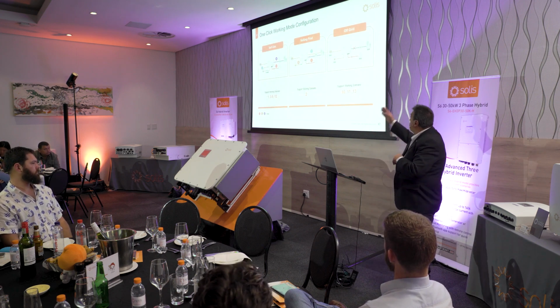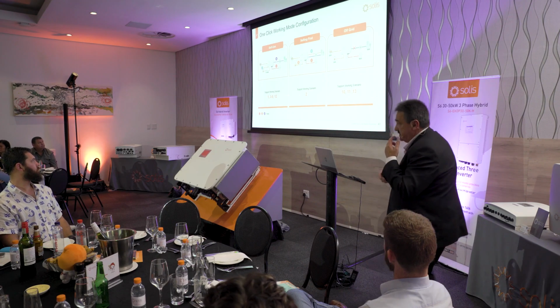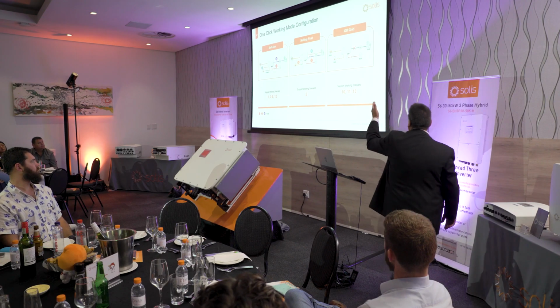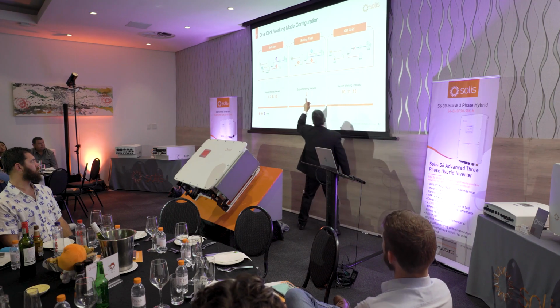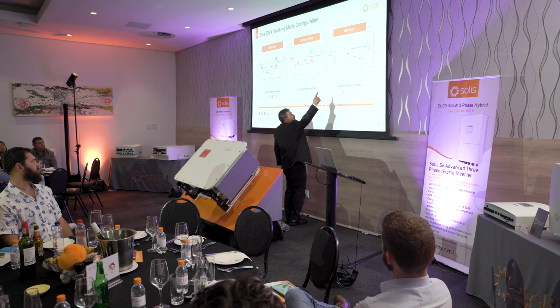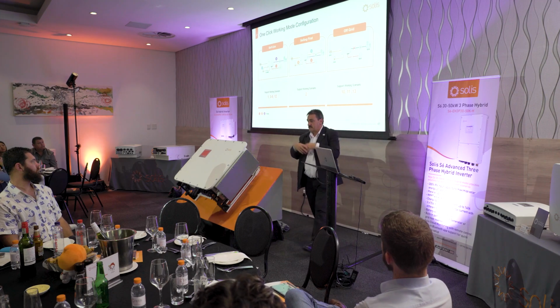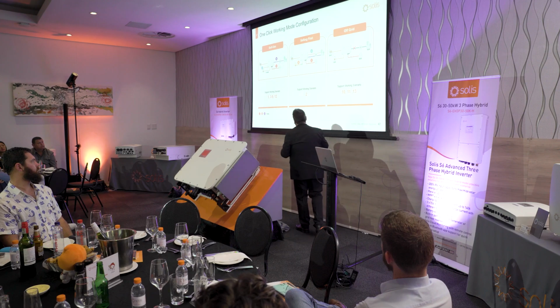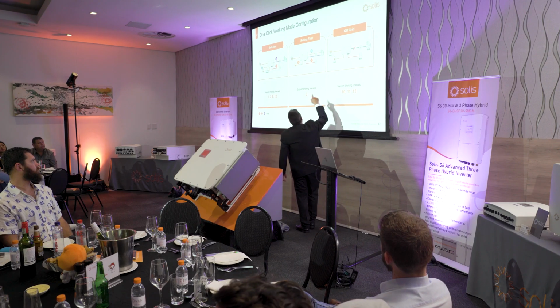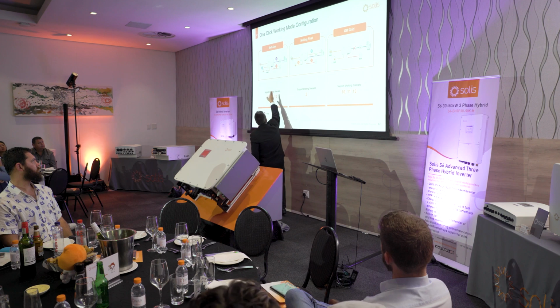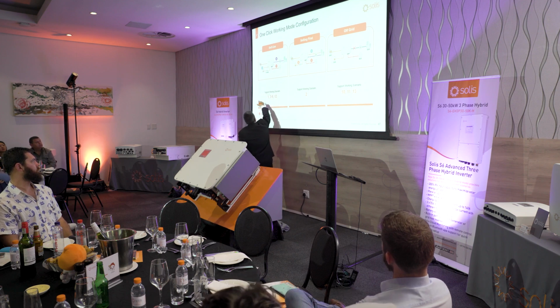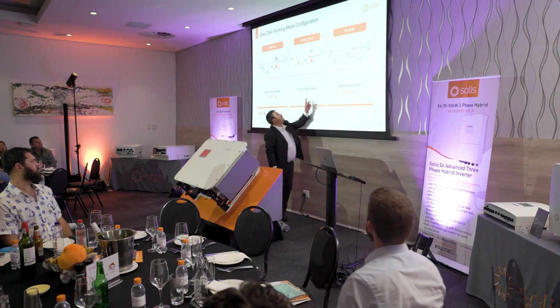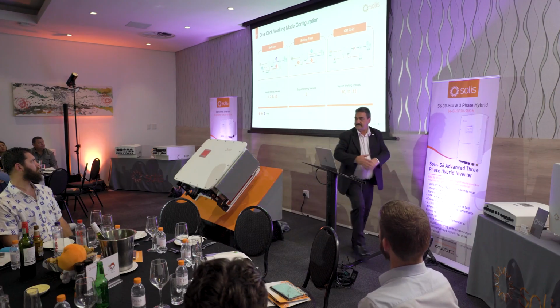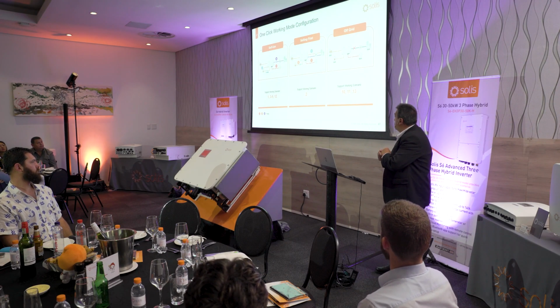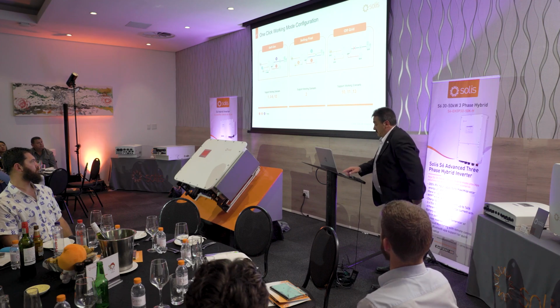Okay, so we were talking about the working mode configuration and the priorities. So everywhere where you see a 1 within the system, it is priority. So load priority, and in an off-grid scenario, everything is priority. Right? All the systems are available, PV is available, batteries are available, the backup load is available, and the power flows freely between any one of those sources. But in self-use, it's backup load, battery, grid. In selling first, load, grid, battery. Okay, make sense? And off-grid, obviously, everything just works.